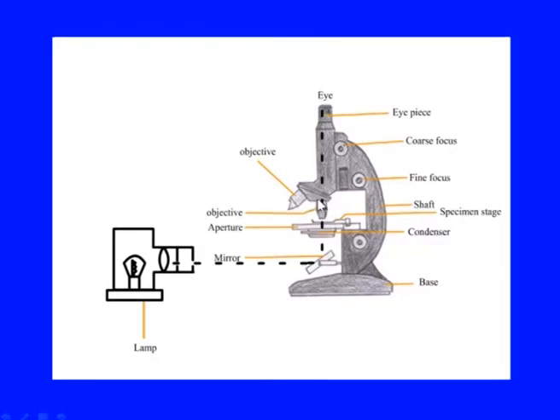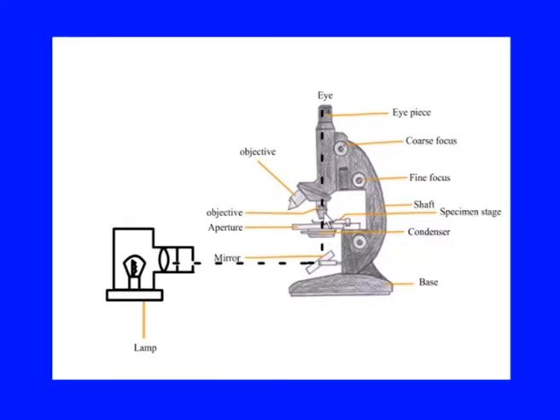The objective lenses are attached to a rotating nosepiece threaded onto the tube, and on the other end is the eyepiece. The nosepiece can be rotated to select objectives of different magnification — 10x, 20x, 40x, or 60x — as per the application. Most advanced microscopes are parfocal, meaning the specimen does not lose focus when changing the objective by rotating the nosepiece.